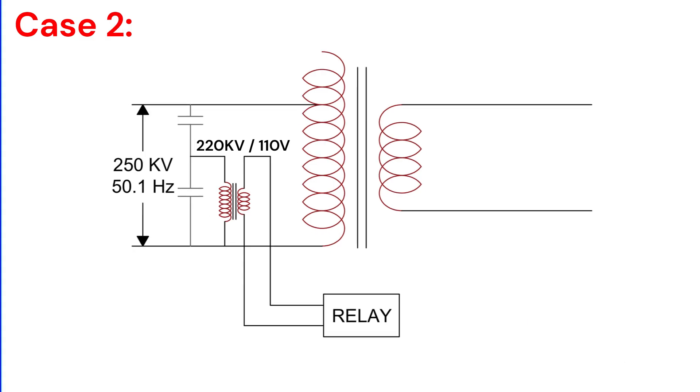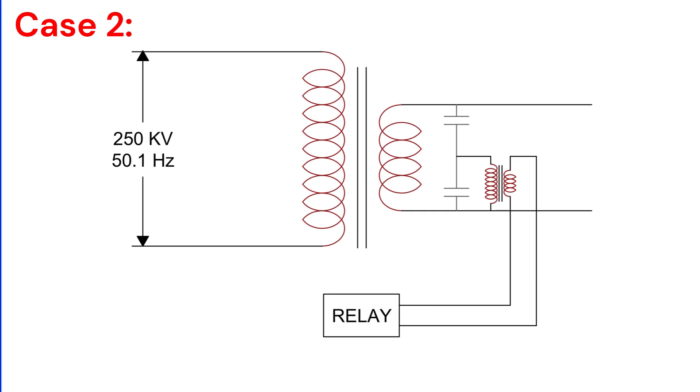Case 2: The transformer has a tap changer. Even if we increase the tap position to reduce the flux, the V/F ratio remains the same because the voltage signal is taken from the primary side PT, so the relay will still trip. But wait, there's a solution. If we take the voltage signal from the secondary side PT, increasing the primary turns will reflect proportionally on the secondary side, preventing unnecessary tripping.